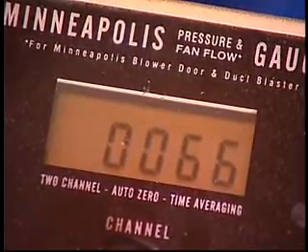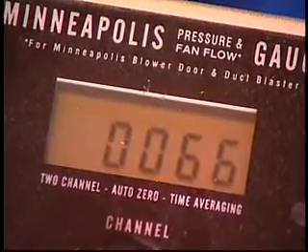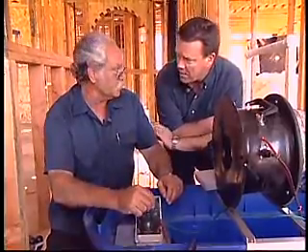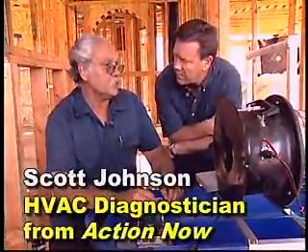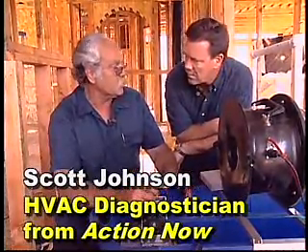The reading is 66 cubic feet per minute, and our maximum allowed amount is 120 CFM — so we're just a little over half of what the test allows. That's pretty good. Where does most leakage usually occur? In this system, as with most, it occurs at the piece of equipment itself.